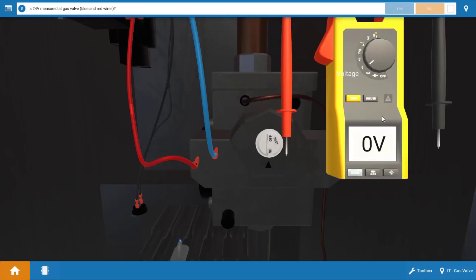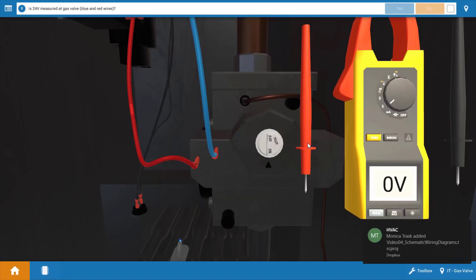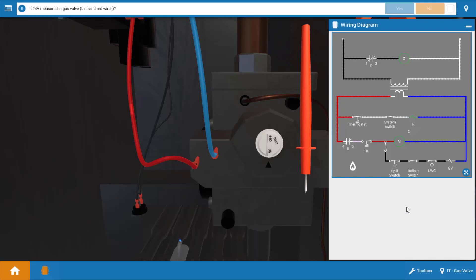Next, it's probably easiest to measure at the gas valve first, but let me show you what we're going to do here. On the wiring diagram, if we click this bottom left icon, you'll see the wiring diagram and all the switches are shown in the current sequence of operations or the way that they would currently be. If we look, we see the gas valve here in the right, and preceding that is a series of safety switches.